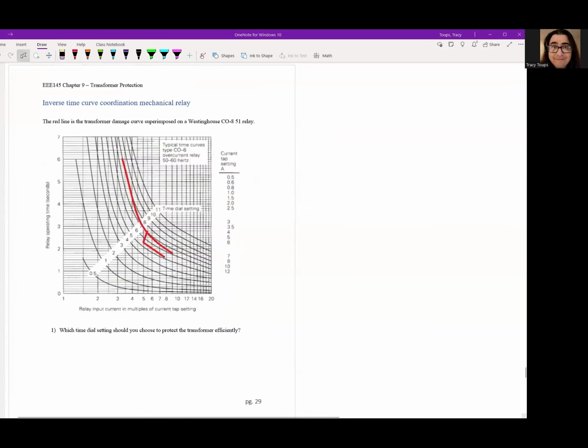Here's an image to show you how to choose the correct time dial. We have these curves that best fit this transformer damage curve right here. Which one should we use? Well, you definitely want the curve that could fit both of these red marks, like the red fork. So I would go ahead with whatever curve is just good enough, and we can trace it back. This is a number 5 curve, so this is a time dial of 5.